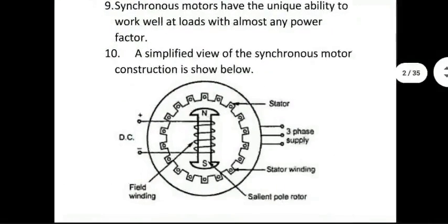So typically, a synchronous motor's cross section conceptually would look like this. The outer part, the stator, has three-phase windings on it in a large number of slots. And the inner part is the rotating part on which magnetic poles are there, which are energized by supplying DC current to the winding on them.